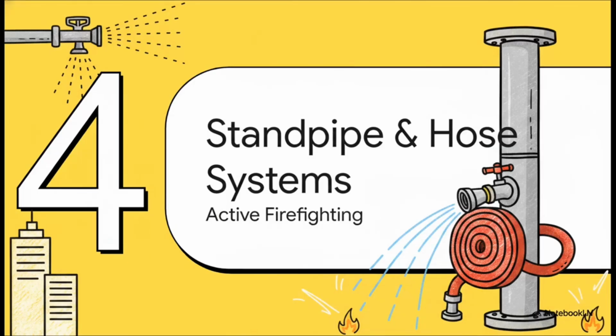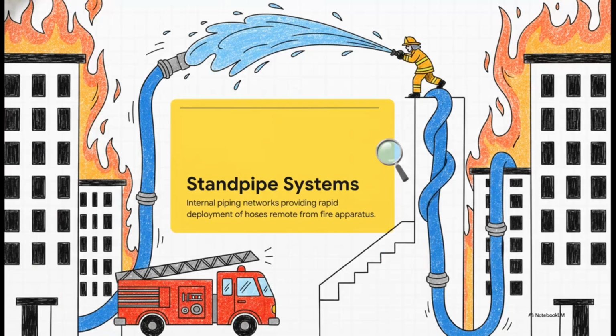All right, on to Section 4, standpipe and hose systems. Alongside those automatic ceiling sprinklers, large structures require a whole other heavy-duty line of defense. Imagine a massive fire breaks out on the 30th floor of a high-rise. Dragging heavy, water-filled hoses up 30 flights of stairs from a fire truck down on the street? Yeah, that is nearly impossible. Standpipe systems solve this exact problem. They are essentially internal water highways, massive vertical pipes running straight up the stairwells of a building. They provide a means for firefighters to rapidly deploy their hoses and operate heavy fire streams at locations that are incredibly remote from their fire engine outside.